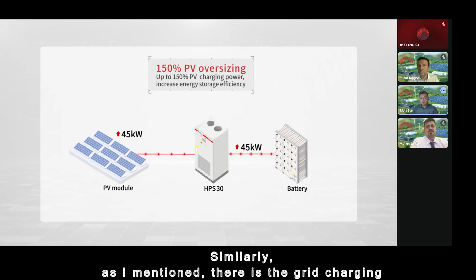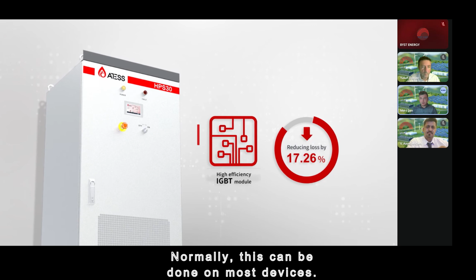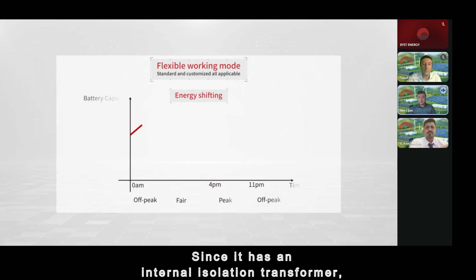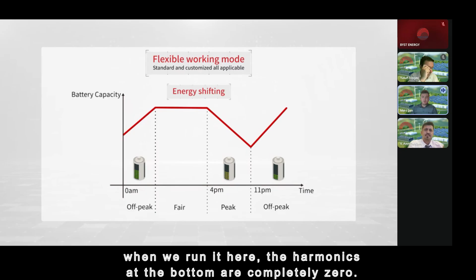These operating modes are for self-consumption, meaning they fully meet our own needs. Similarly, as I mentioned, there is the grid charging and discharging sales mode, peak shaving mode, and the microgrid island operating mode. I would like to explain this microgrid mode in more detail. Microgrid is important in the following way. Normally, this can be done on most devices. It is an operating mode, but it has a nice feature. Since it has an internal isolation transformer, when we run it here, the harmonics at the bottom are completely zero.